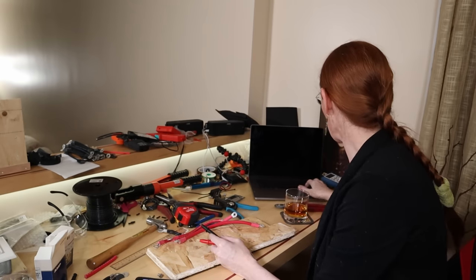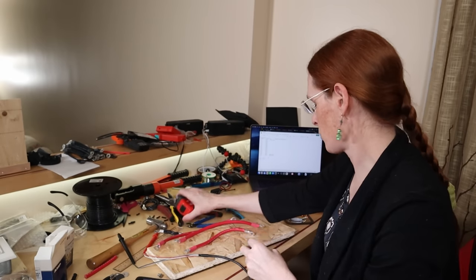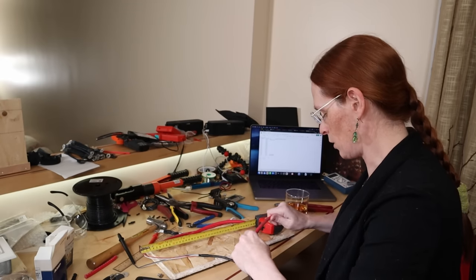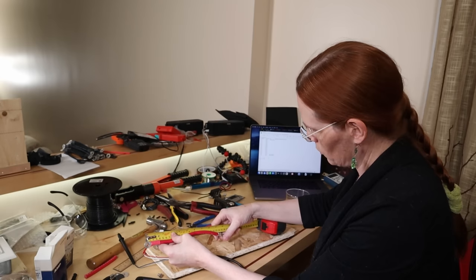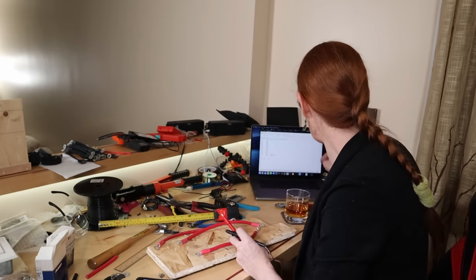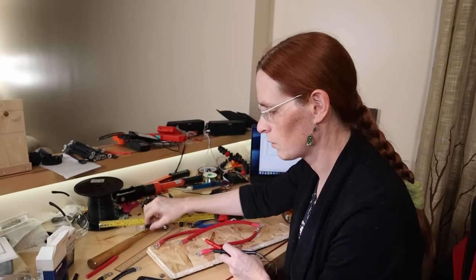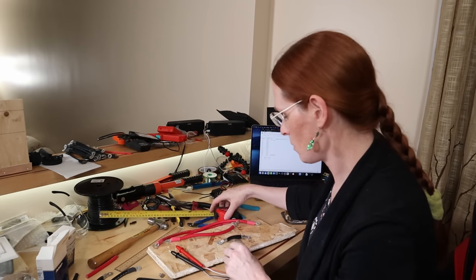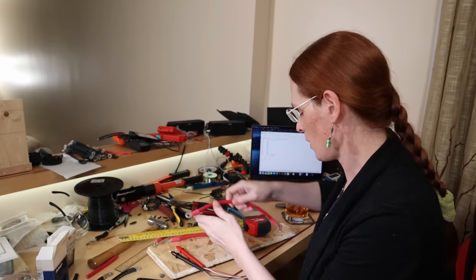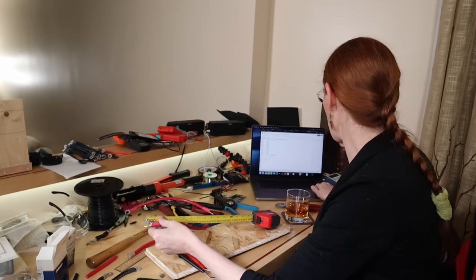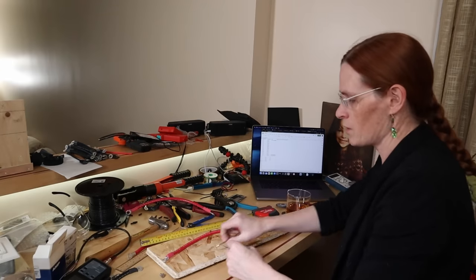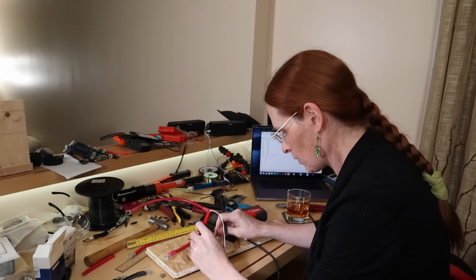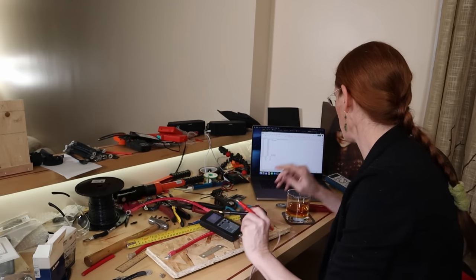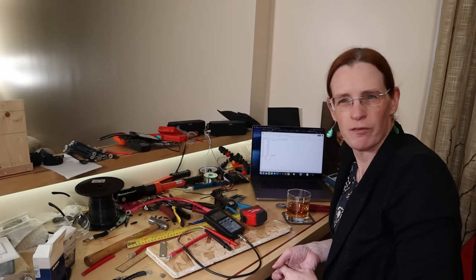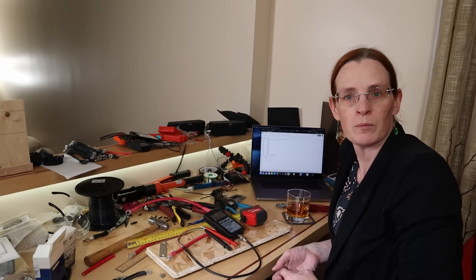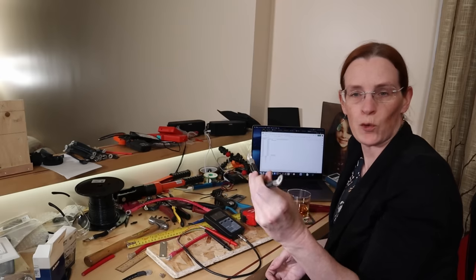0.15 on this one, let me write this down. Where's the measuring tape? I'm wondering if we can find a correlation. Let's call it 235, 0.22, 0.23 — let's call it 0.22. The shorter one: 0.07, and that length is, let's call it 75. Do I have a longer cable? This is my longest cable — 305, 0.28, 0.29, let's call it 0.29. Solid bus bar is 60 — flip it over so I'm not on the scraped-off part — 0.03. I know this isn't a lot of data, but it looks very roughly to be about 0.1 milliohm per centimeter of either 4 gauge or 4x10 gauge.